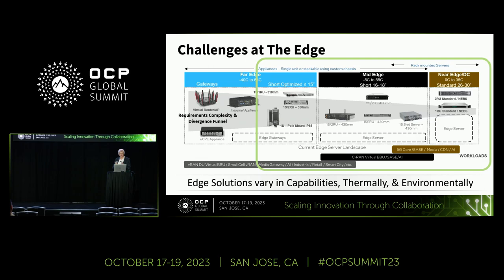For us, the area in green is the focus for this talk and for how we want to present modular systems in this next step of bringing modularity to servers. From a size perspective, the mid-edge takes us down to around 430 to 480 millimeters, but going into the far edge we need systems as small as 310 millimeters to be installed on cellular telephone poles or in the base system. This creates a much more complex design problem with thermal, cabling, and power solutions. Today, OEMs address this with their own unique solutions — so how would we bring what we learned in DCMHS to the edge?